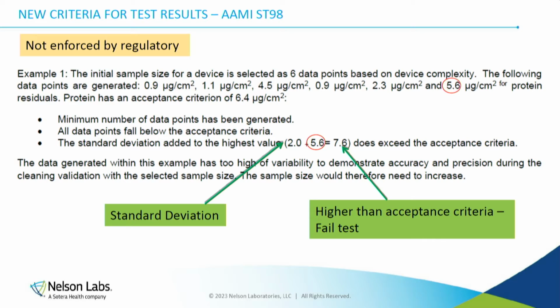So from here on, with any validations that you do, you want to look at your data, because if you see 0.9, 1.1, 4, that should already alert you that there is something happening. Why aren't they similar? These are made-up numbers, straight out of the standard. But if you ever see numbers like this, that is where you question what's happening, because there's something wrong. If the standard deviation of those 6 data points is 2, it's added to 5.6 and you get 7.6, it's a failure now. So you would have passed earlier, before the standard came out.